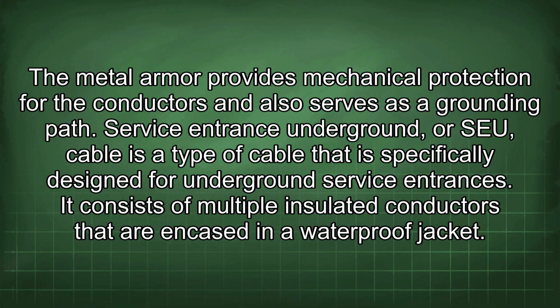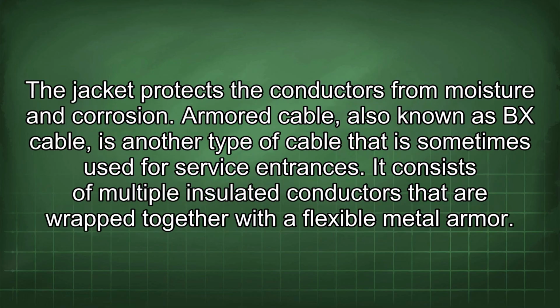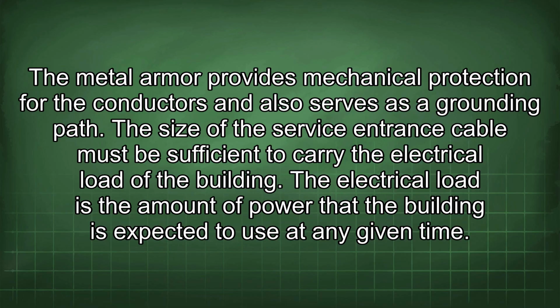Service entrance underground, or SEU, cable is a type of cable that is specifically designed for underground service entrances. It consists of multiple insulated conductors that are encased in a waterproof jacket. The jacket protects the conductors from moisture and corrosion. Armored cable, also known as BX cable, is another type of cable that is sometimes used for service entrances. It consists of multiple insulated conductors that are wrapped together with a flexible metal armor. The metal armor provides mechanical protection for the conductors and also serves as a grounding path.